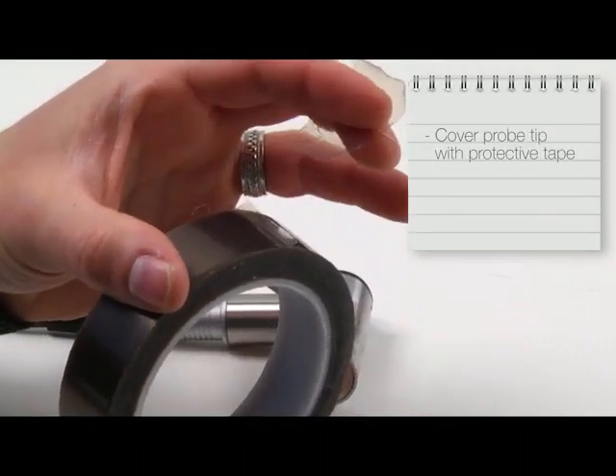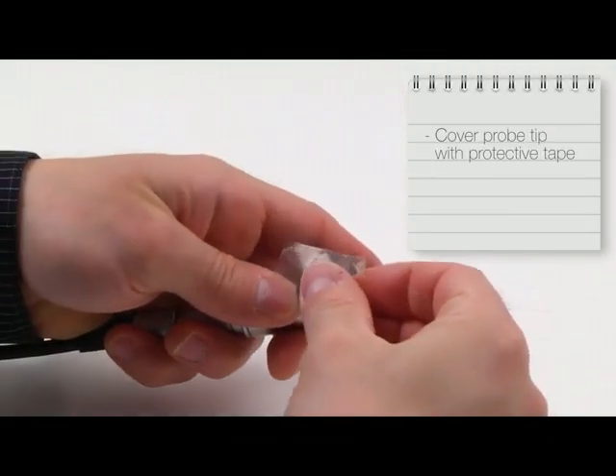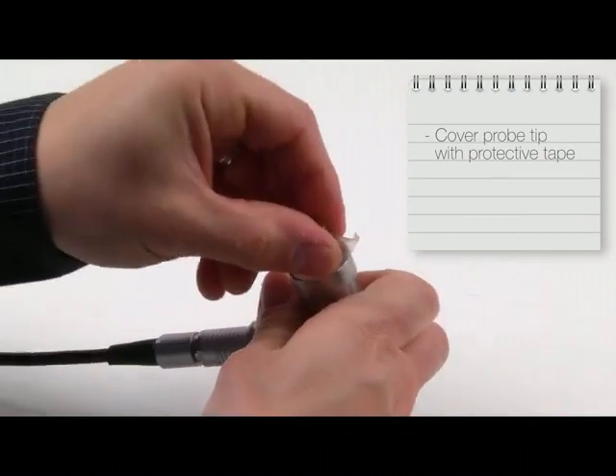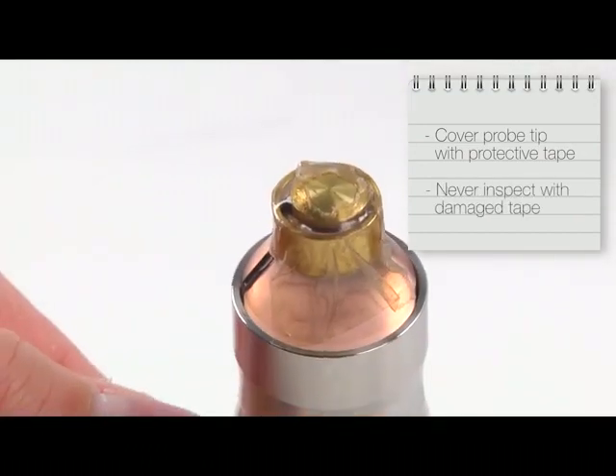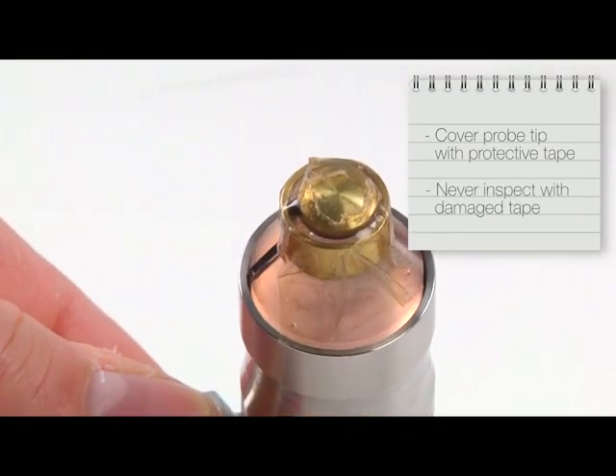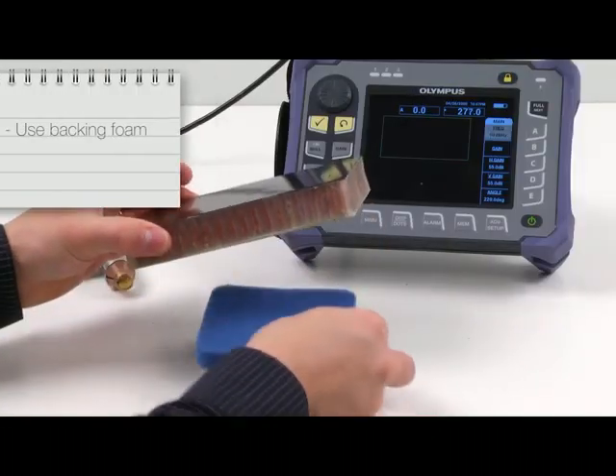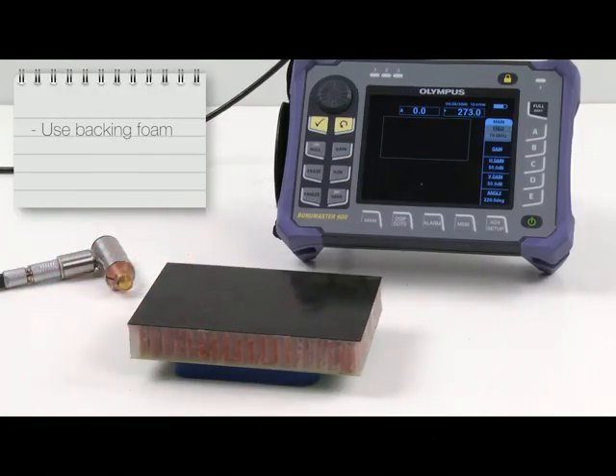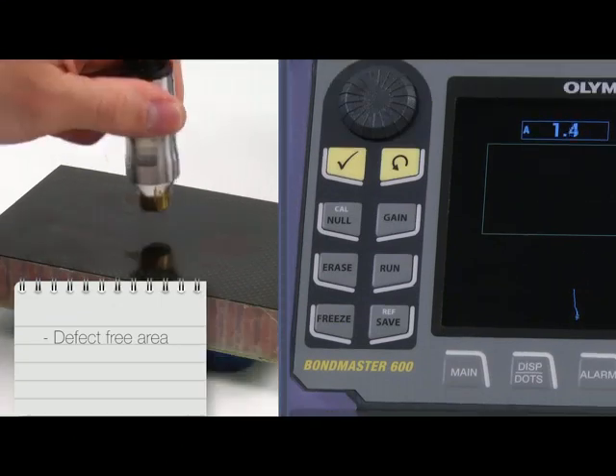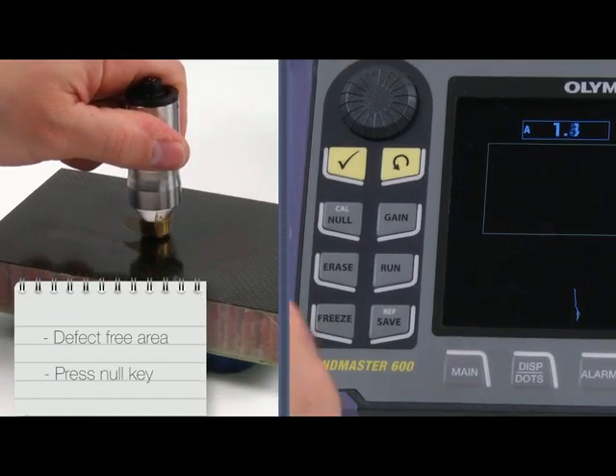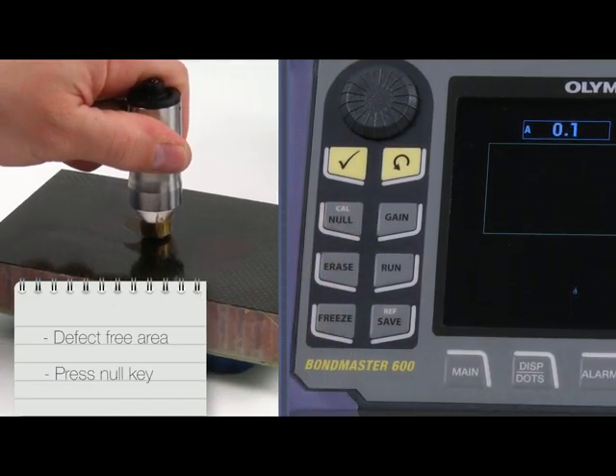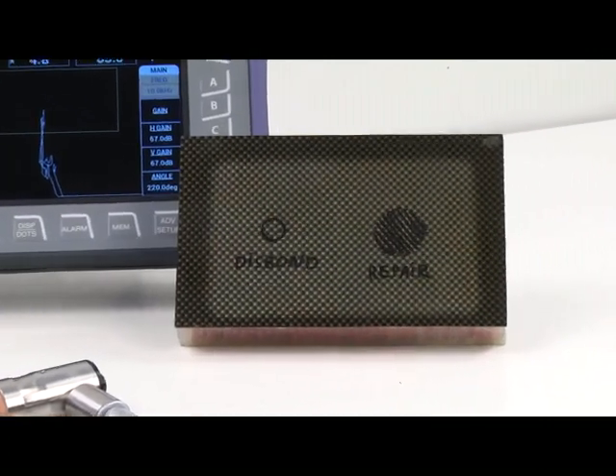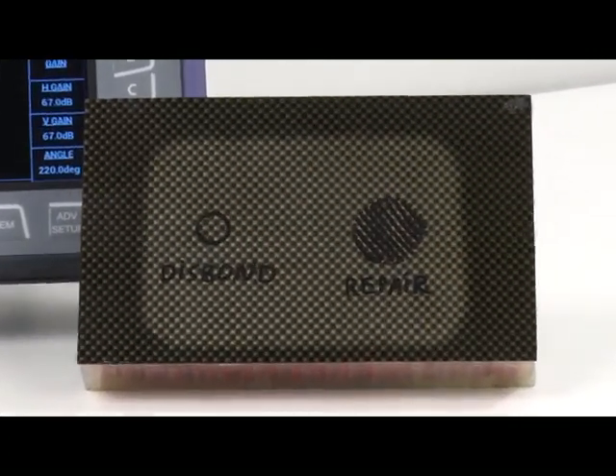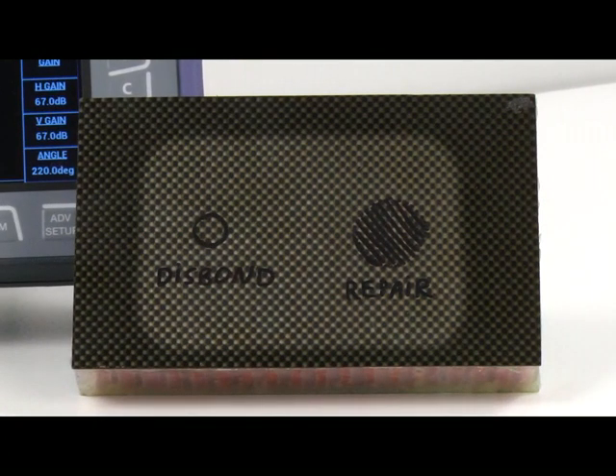Ensure that the probe tip is covered with Teflon tape or an equivalent protection film. Never inspect with damaged tape, as this will scratch the surface and damage the probe. You may use backing foam to achieve better results. Place the probe on an area free of defects and press the null key. It's important to know where the simulated defects are located to avoid mistakes during calibration.